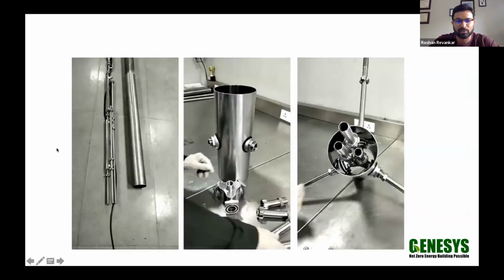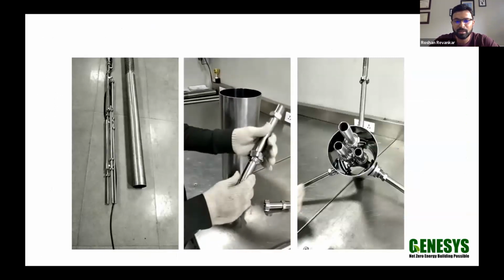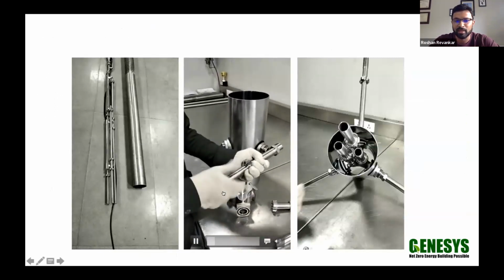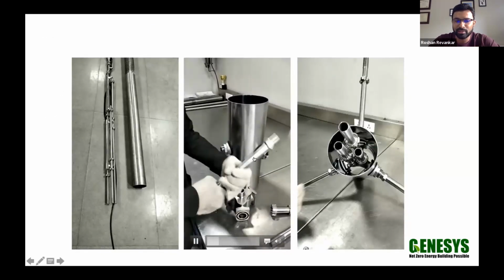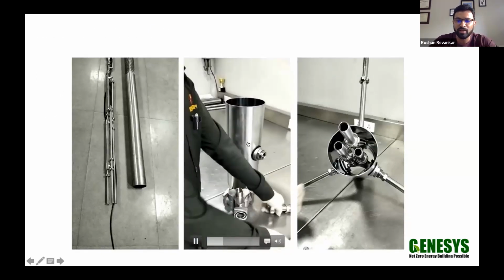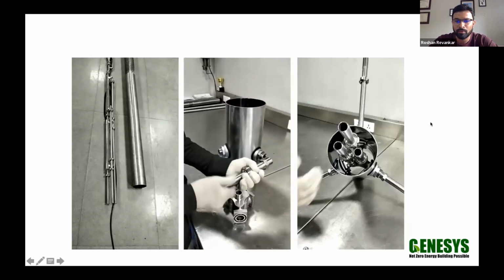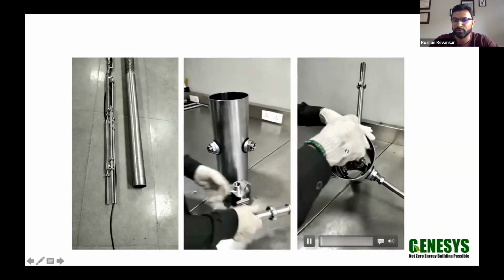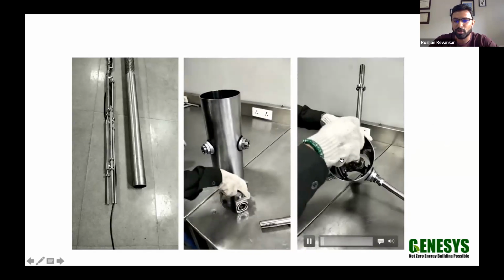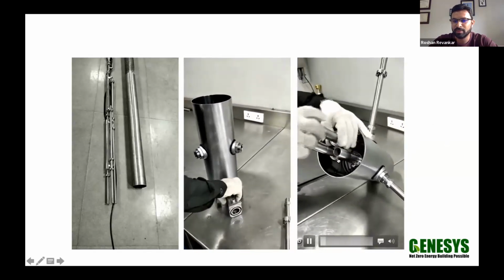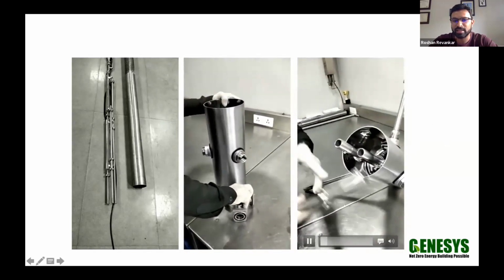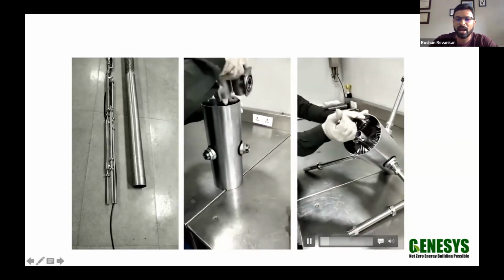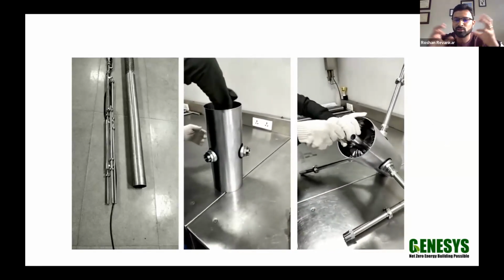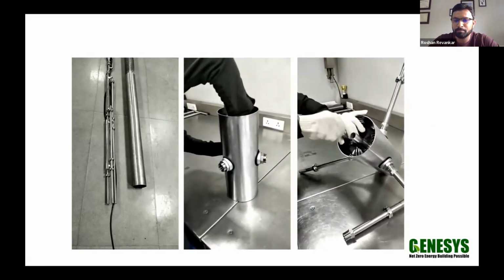So here is the actual product. This is a 6-ton unit. There are a few videos which I'll just walk through. What you're seeing in the middle is what we call a pitless adapter unit, so this sits on top of the well. This is how you unscrew 3 pipes. There is a supply and return, and the rest of the connections between the pitless adapter and the CLAD unit is all HDPE pipe, plastic pipe.